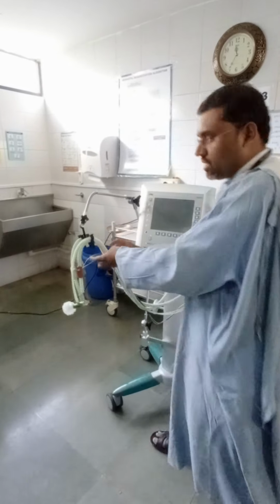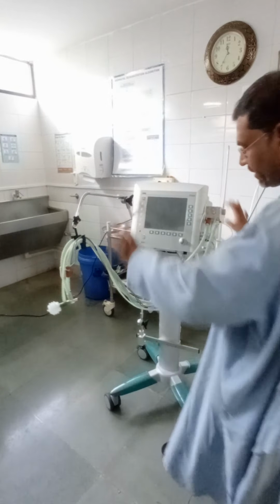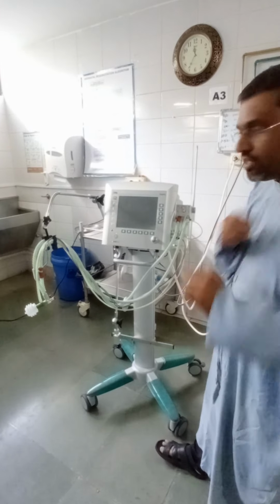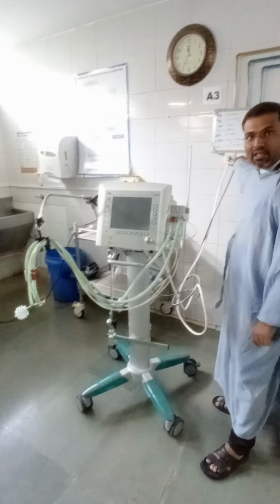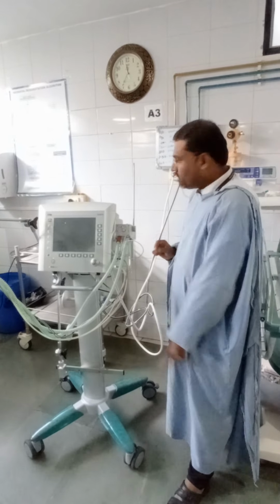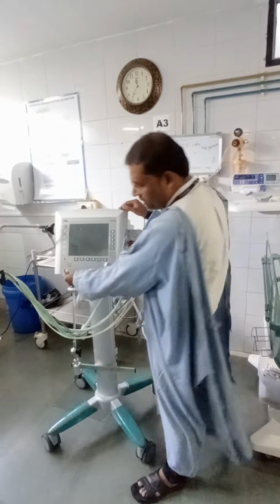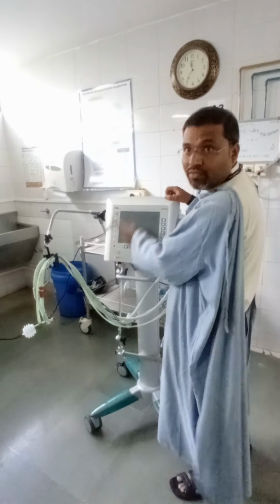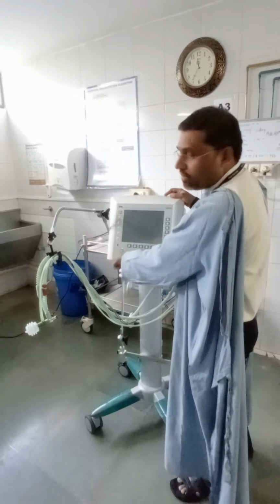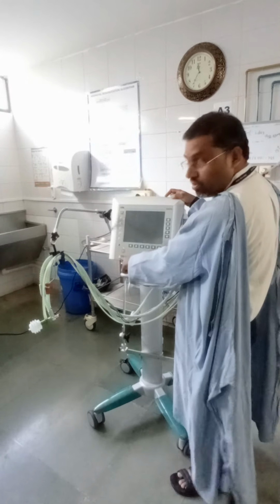So this is your basic arrangement of the ventilator before connecting to the patient. Again, I am just repeating within the 1 minute. First, you have to connect the tubings. Second, lock the wheels. Connect your power cord. Check whether the power cord is connected properly or not. If it is not connected, the signal will not appear. If it gets connected properly, the signal will appear.